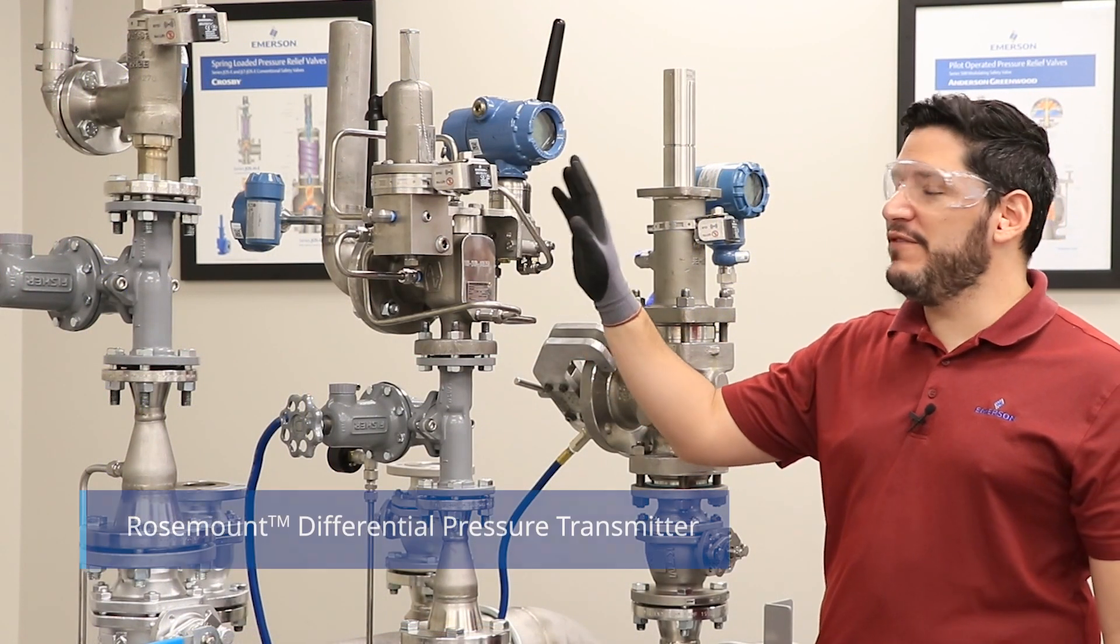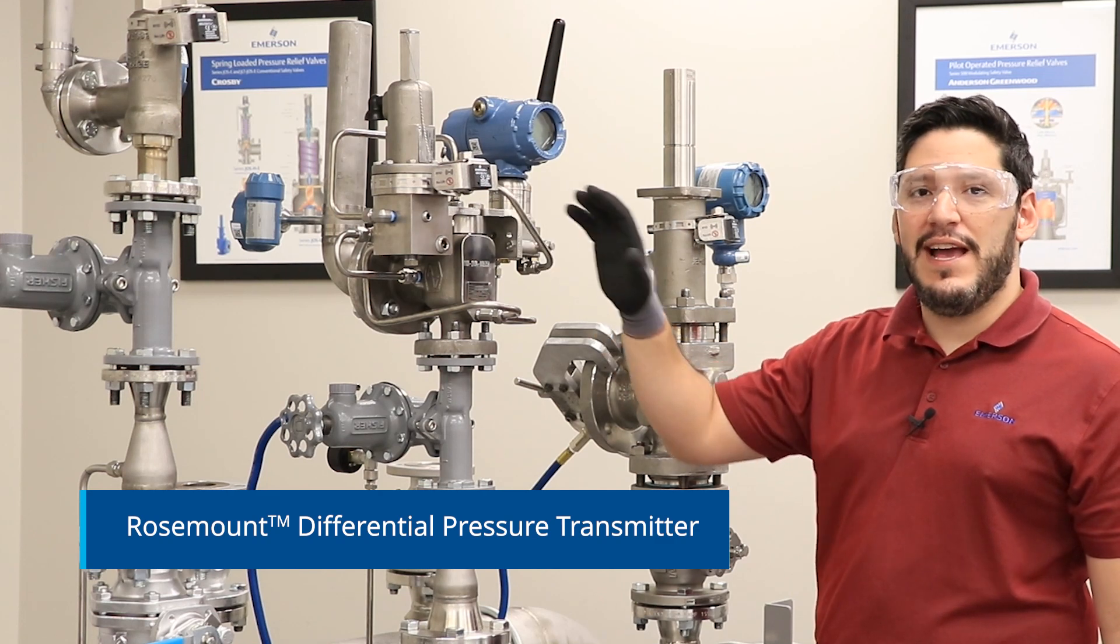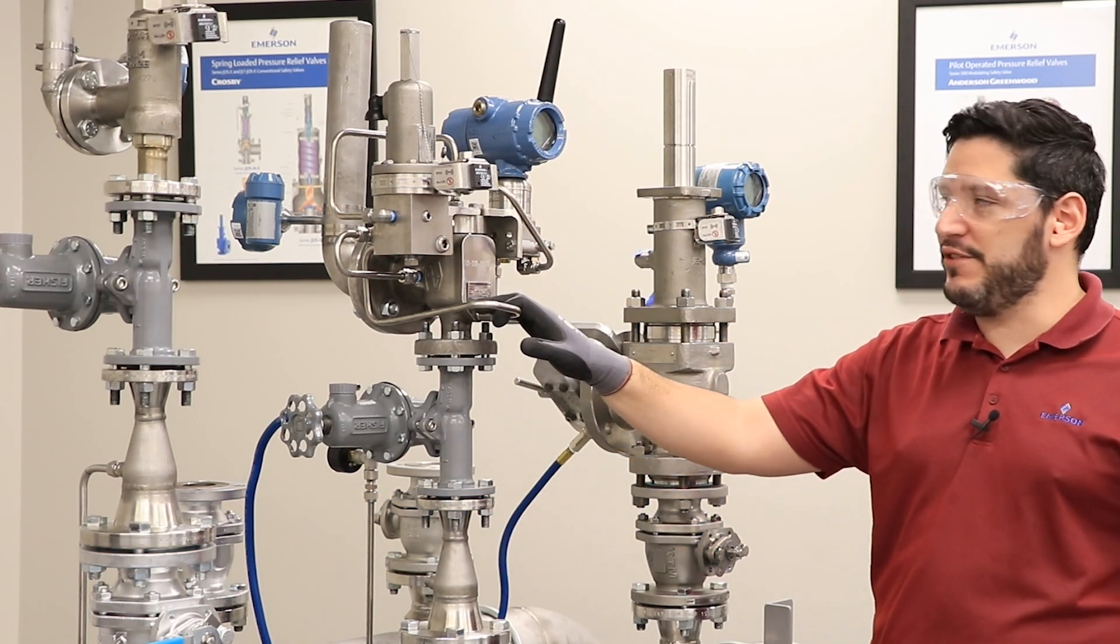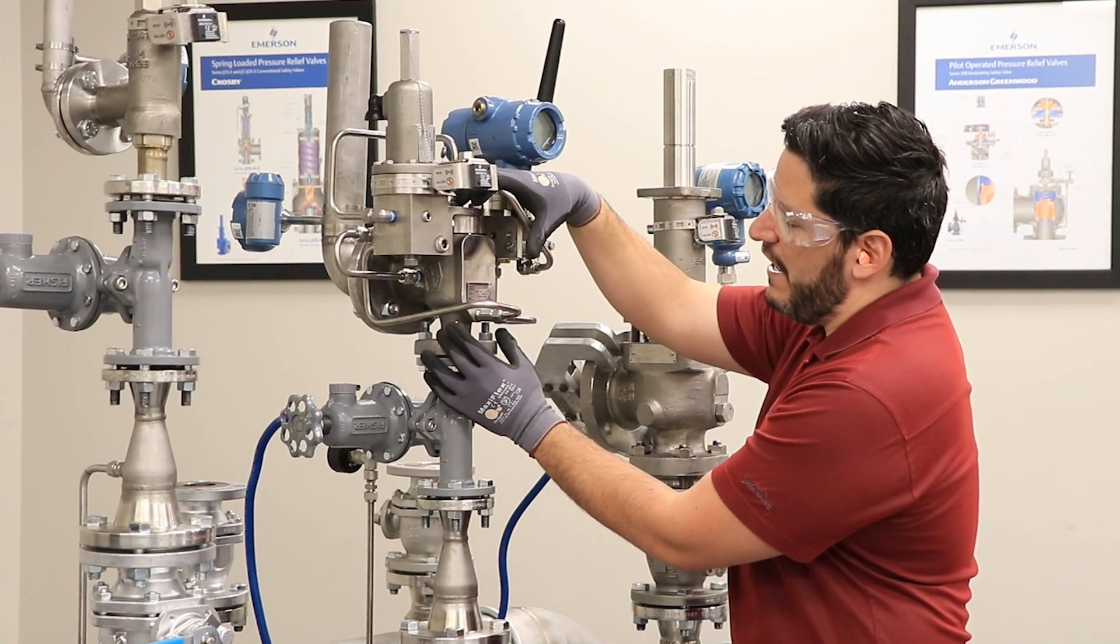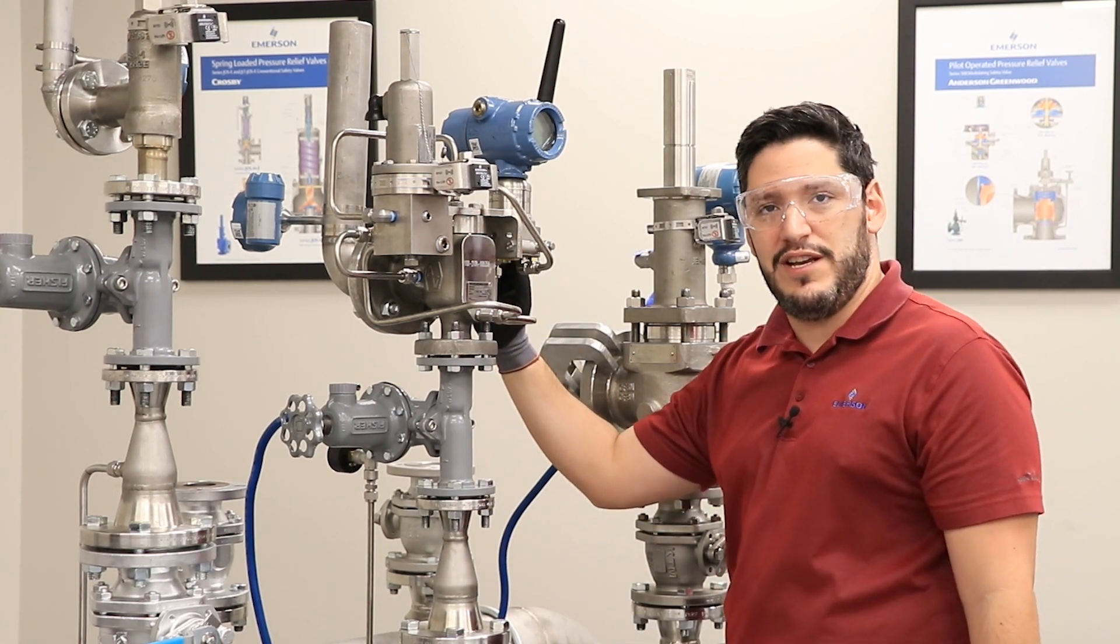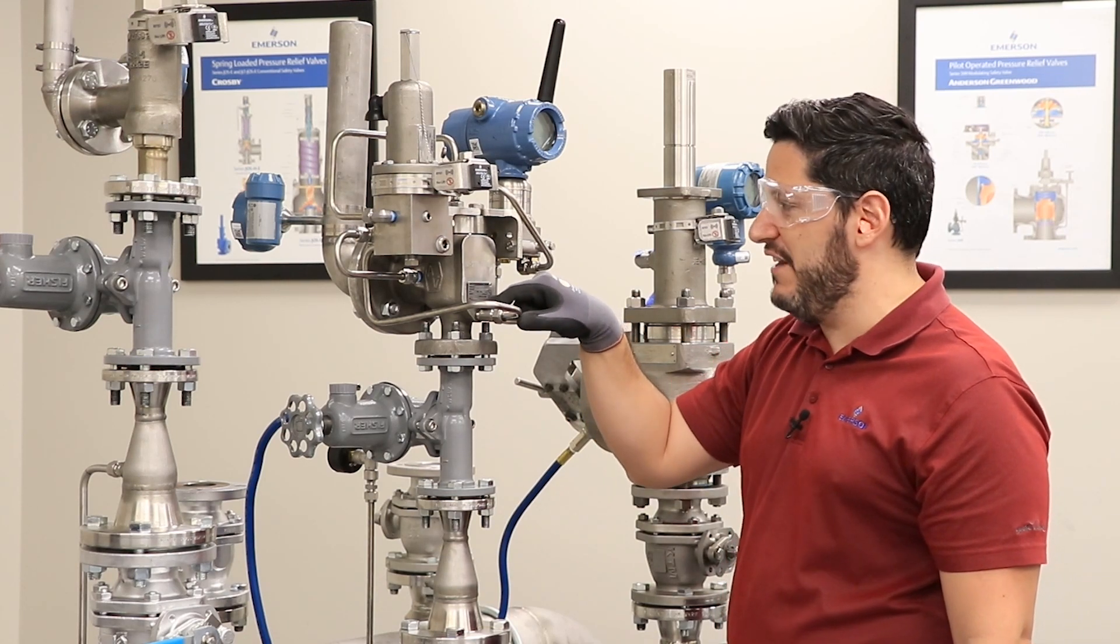This is our differential pressure transmitter, which we use for our high pressure and low pressure Emerson pilot operated relief valve monitoring. The way that this works is the main valve has a pressure pickup port. We take the high side of the differential pressure transmitter into the pressure pickup port at the inlet of the main valve.